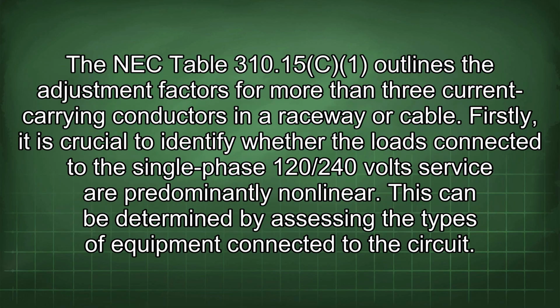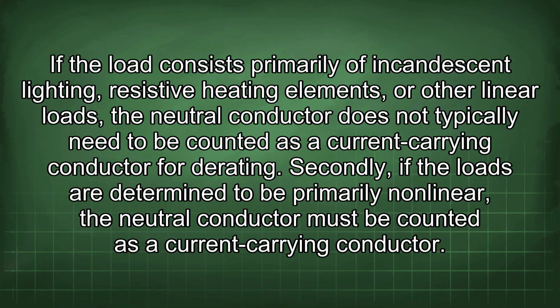The NEC Table 310.15 outlines the adjustment factors for more than 3 current-carrying conductors in a raceway or cable. Firstly, it is crucial to identify whether the loads connected to the single-phase 120/240 volt service are predominantly nonlinear. This can be determined by assessing the types of equipment connected to the circuit. If the load consists primarily of incandescent lighting, resistive heating elements, or other linear loads, the neutral conductor does not typically need to be counted as a current-carrying conductor for derating.